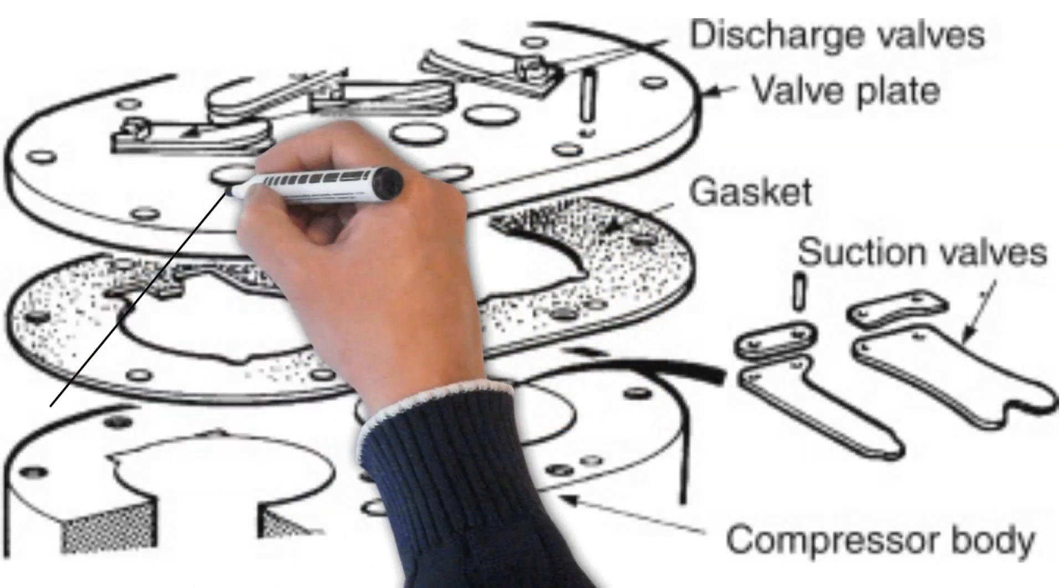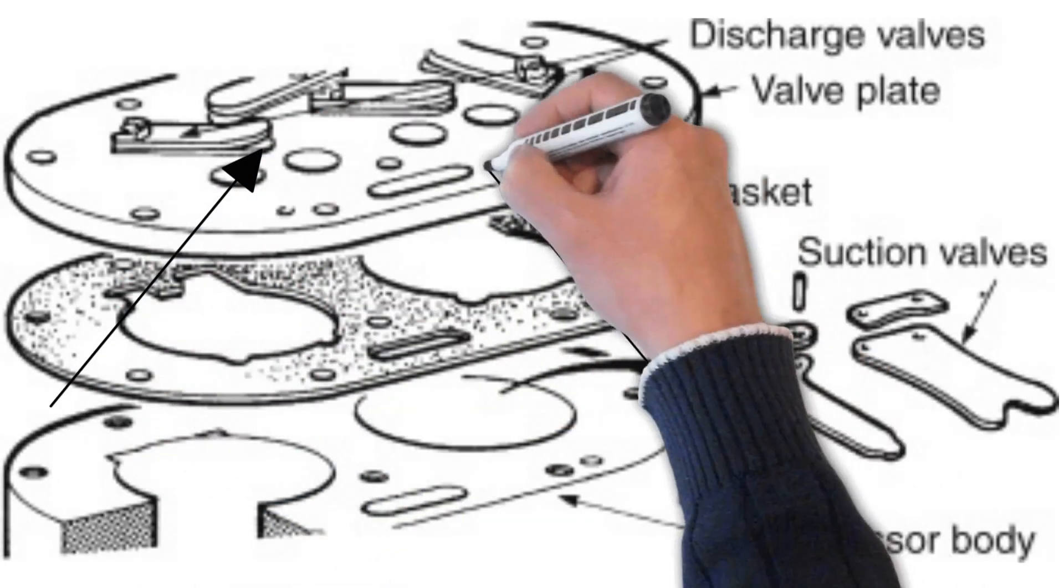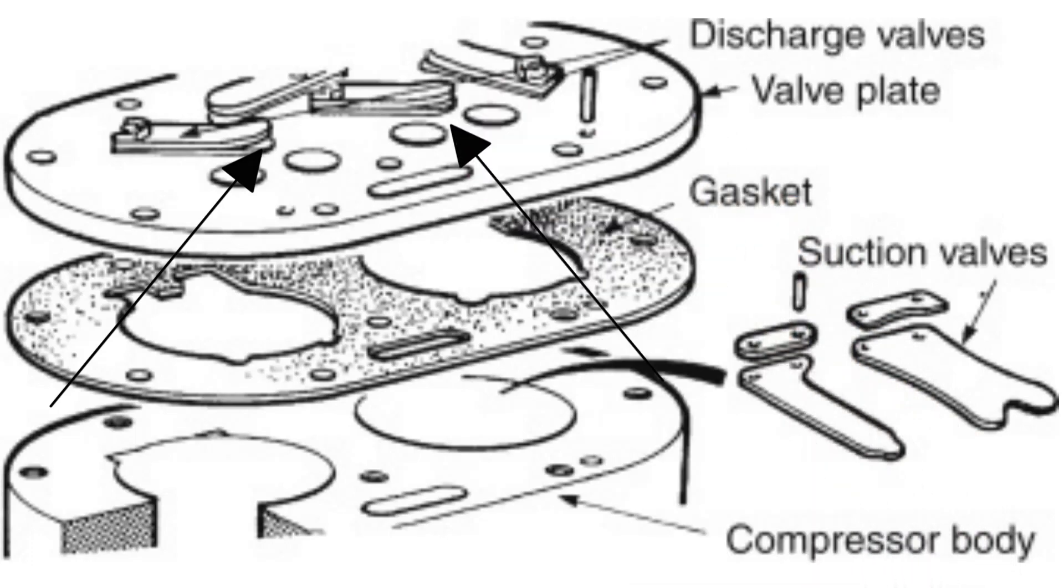This sludge tends to collect in hotter areas, usually the exhaust valve plate, and if allowed to build up, can prevent the exhaust valves from closing properly.